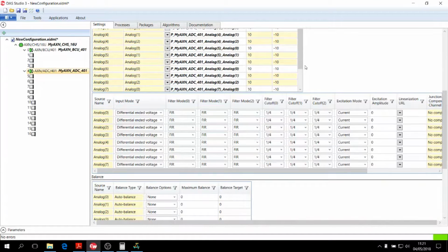And going down to the different channel input modes, you define the input mode here. You can choose on a channel by channel basis: differential, single-ended, full bridge, half bridge, thermocouple, RTD 2 or 4, RTD 3-wire, AC coupled or ICP sensor. For potentiometer you would use half bridge mode. For each filter tap point then there is settable a filter mode of FIR filter, IIR 8 or IIR 16. That's configurable on each filter tap point.